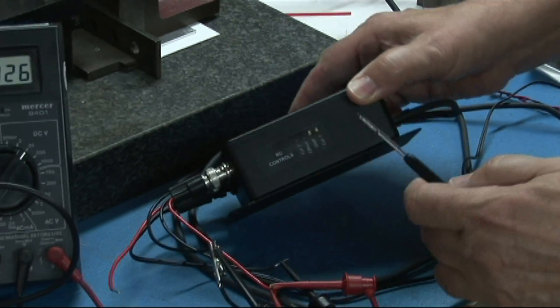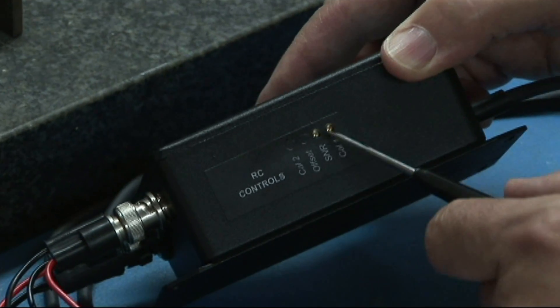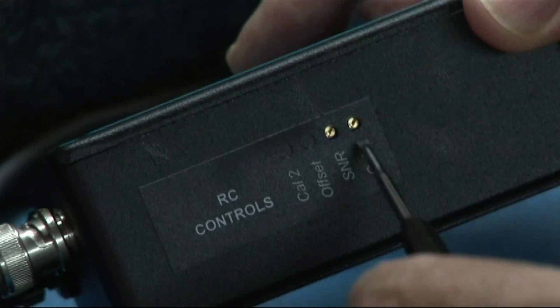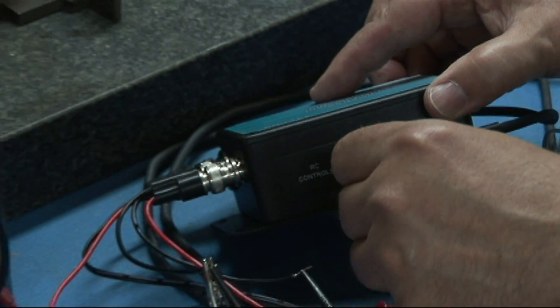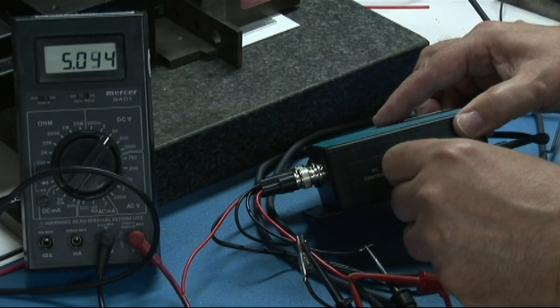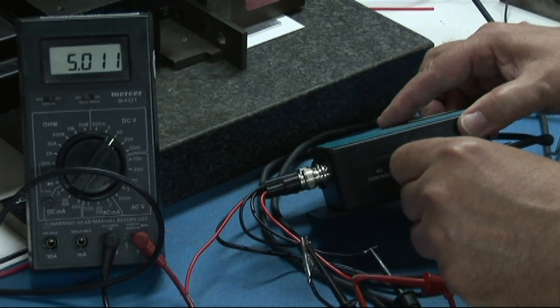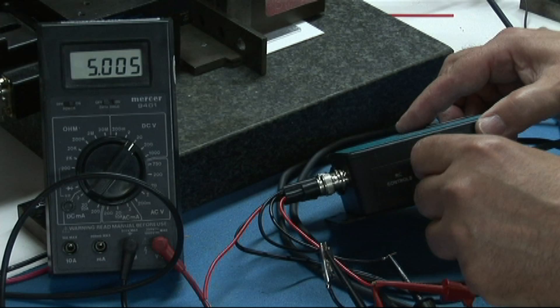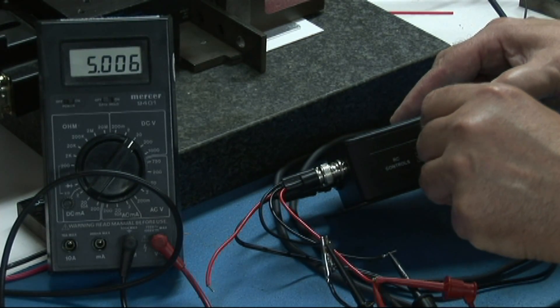And the sensors we've delivered to you, this CAL-1 control, it may be blocked off. If it is, you just need to lift this label up and get underneath it, and you'll get to this little trim pot. And we're going to set this output to as close to five volts as we can get it. So let's say that's about as good as we're going to do here.